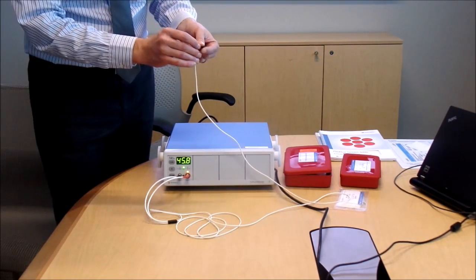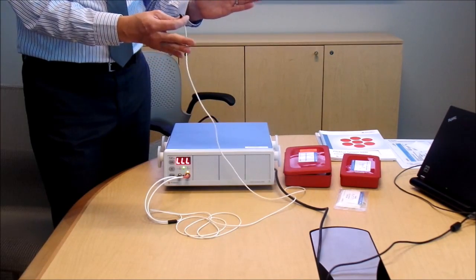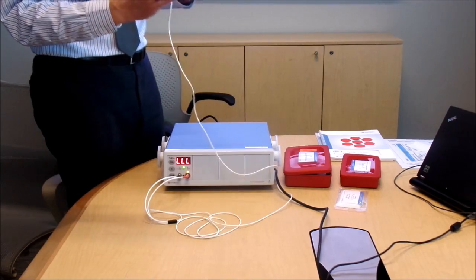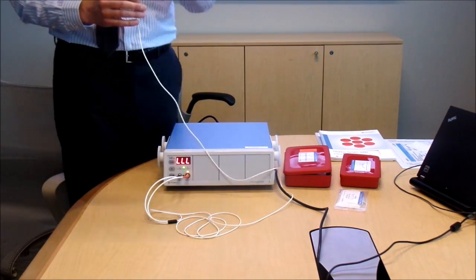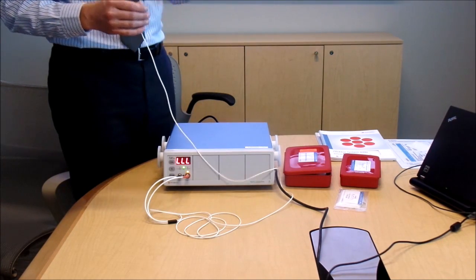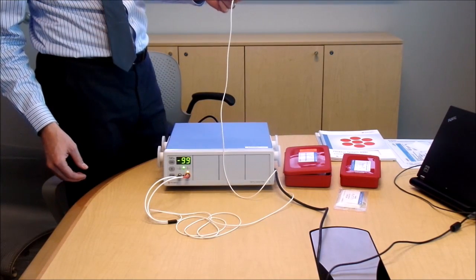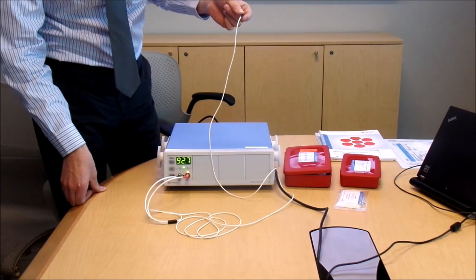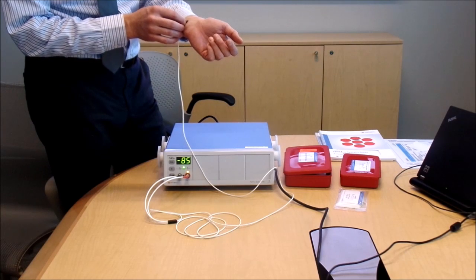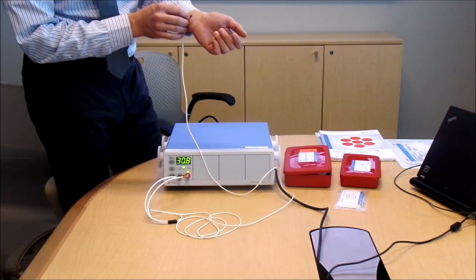And you will find, just like Dr. Yuen said, that when you're on a certain type of tissue or perhaps a certain type of flap, you tend to be within a ballpark. Even though the number is arbitrary, there is some consistency to it. If you're on the same type of skin, for example, you typically land in the same ballpark region. And when it comes to flap survivability, you have a pretty well established method of, you know, anything going below a certain number or dropping a certain amount in a certain time frame, definitely something to be aware of and watch out for. But as an example, typically if I put this on my fingertip and let the number stabilize here, you can be somewhere between 100 and 300 perfusion units oftentimes. If I go on the forearm skin, a normal level might be between 5 and 15 perfusion units. So just different types of skin can have very different levels of perfusion oftentimes.